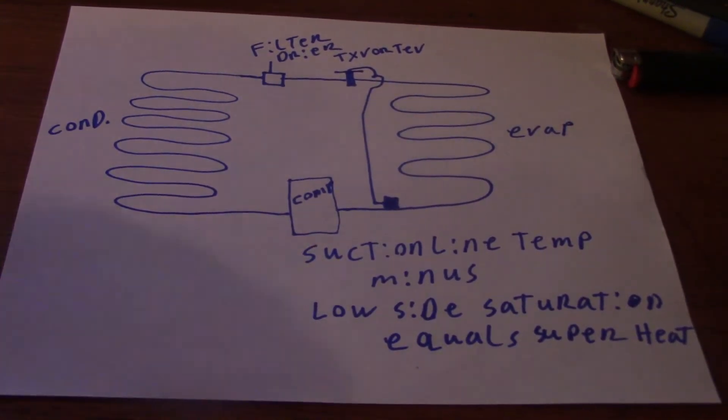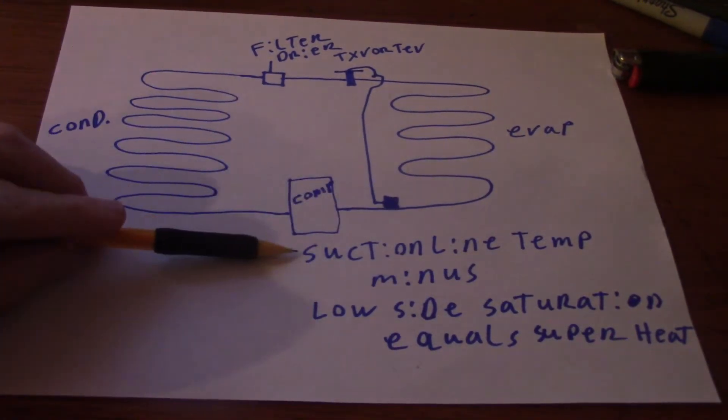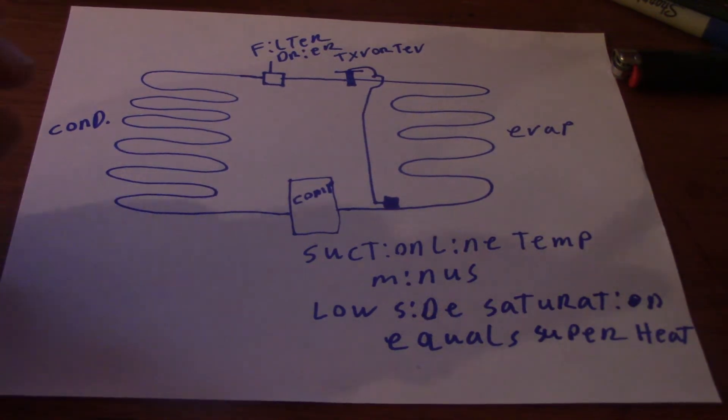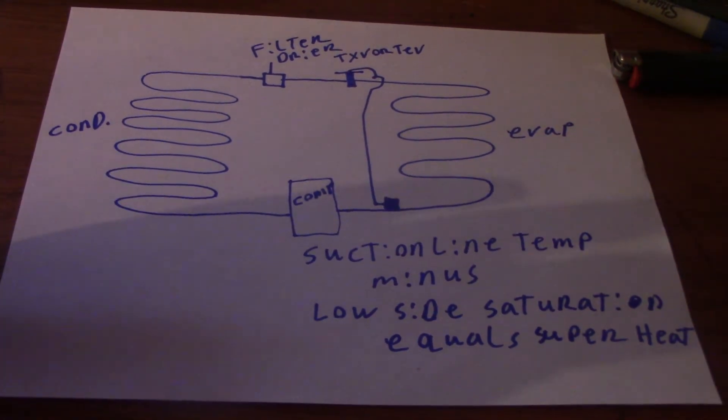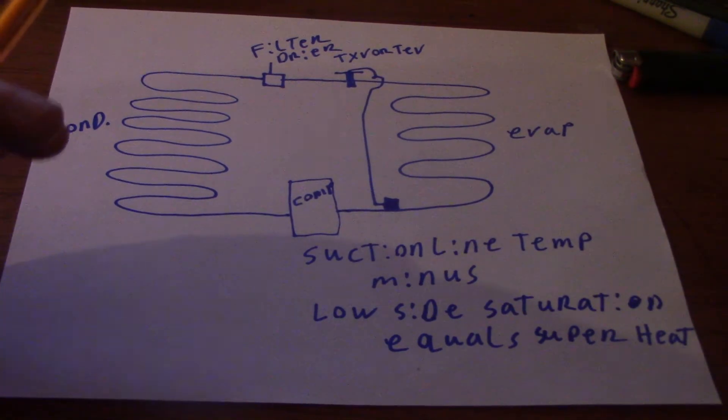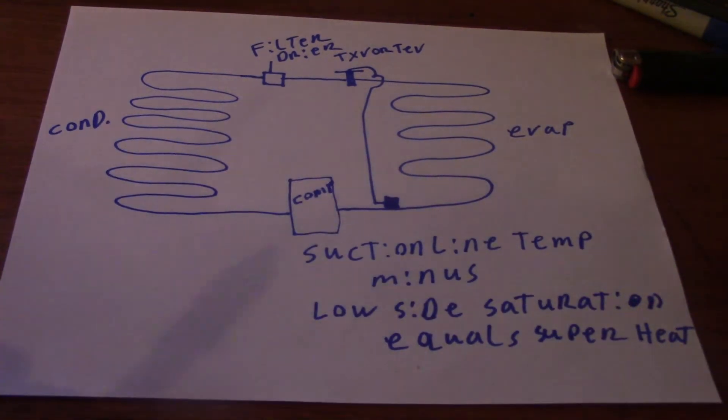So superheat, you calculate it as it says here, suction line temperature minus your low side saturation. That will equal your superheat. What you're calculating by that is how much heat has been added to the refrigerant after it's boiled off in the evaporator.